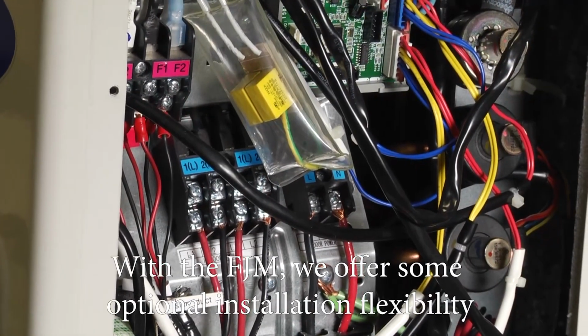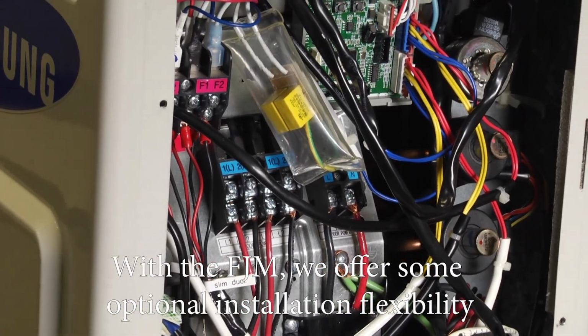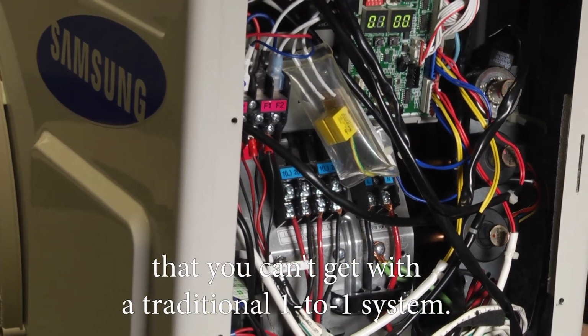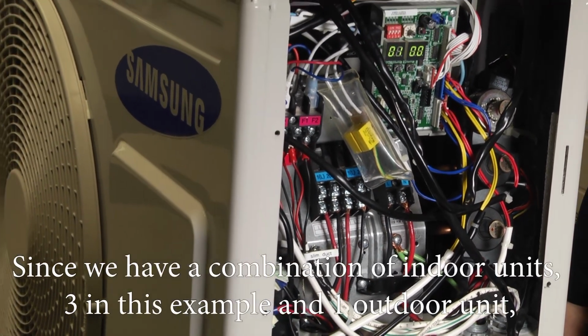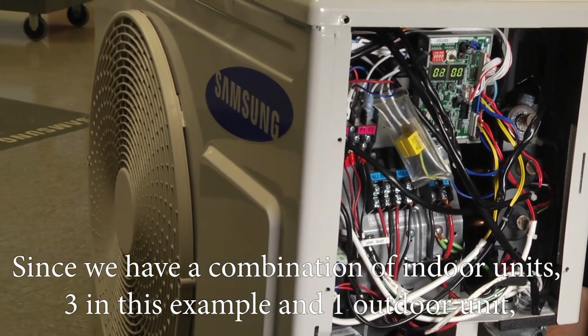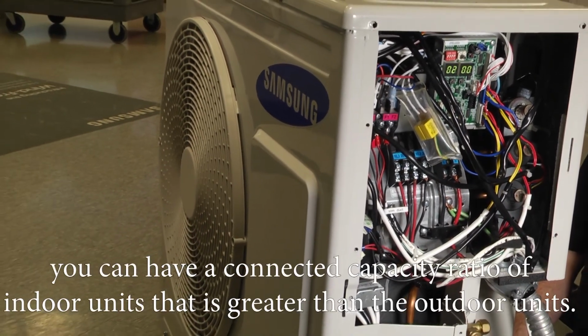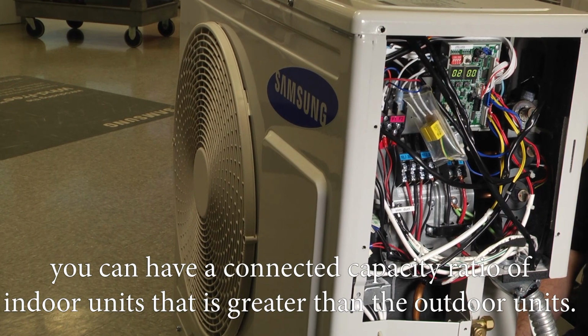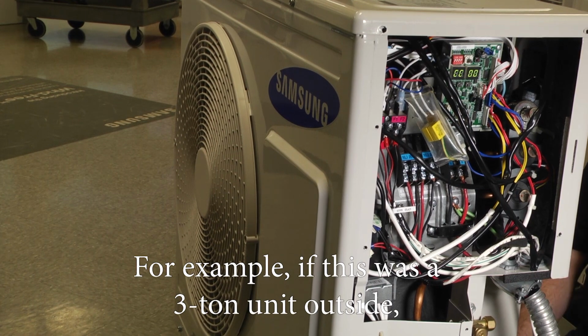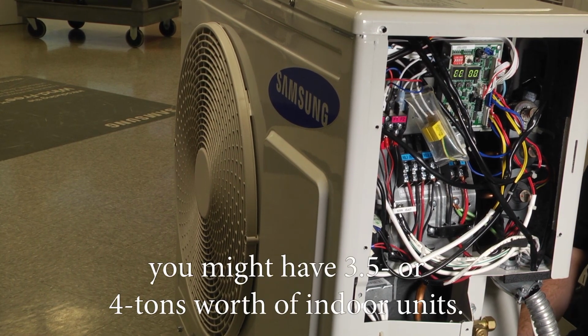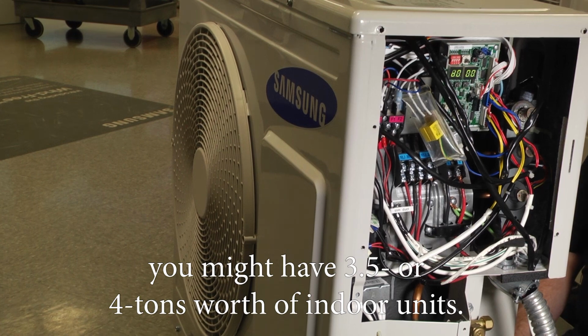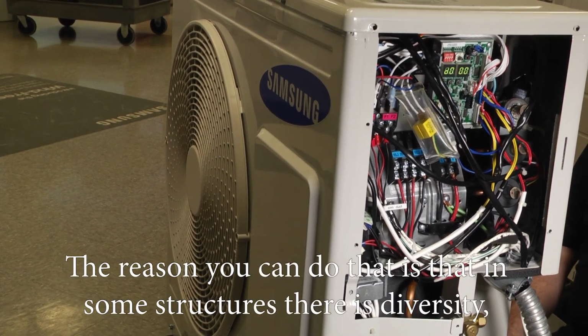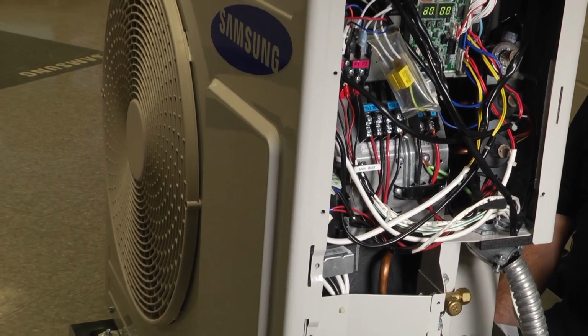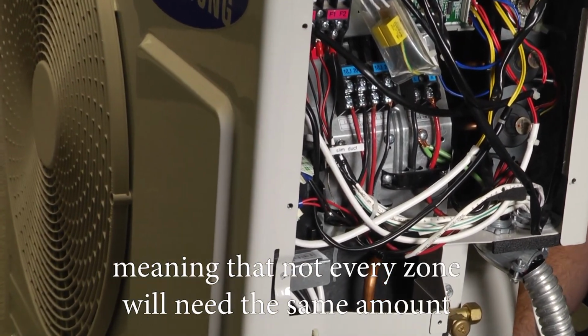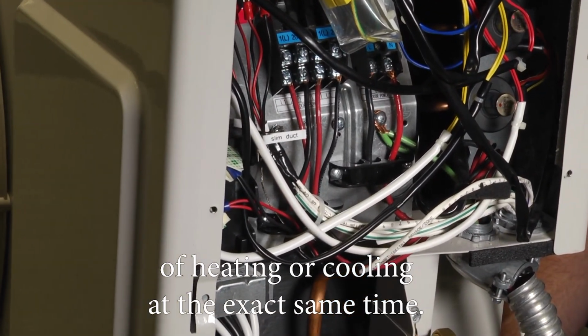So with the FJM, we offer some optional installation flexibility that you can't get with a traditional 1-to-1 system. Since we have a combination of indoor units, 3 in this example and 1 outdoor unit, you can have a connected capacity ratio of indoor units that is greater than the outdoor units. For example, if this was a 3-ton unit outside, you might have 3.5 or 4 tons worth of indoor units. The reason you can do that is in some structures there's diversity, meaning that not every zone will need the same amount of heating or cooling at the exact same time.